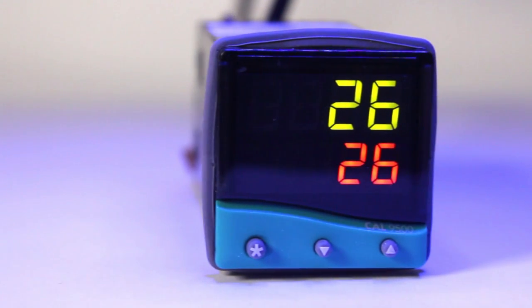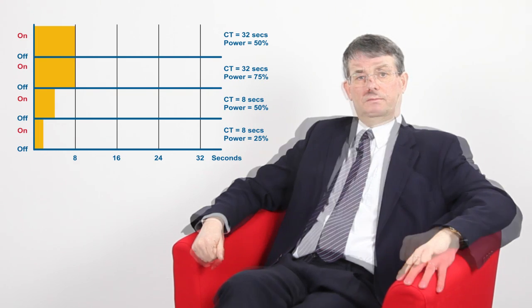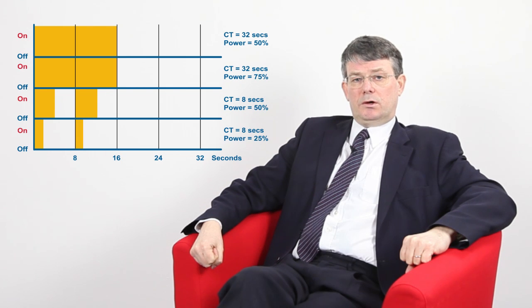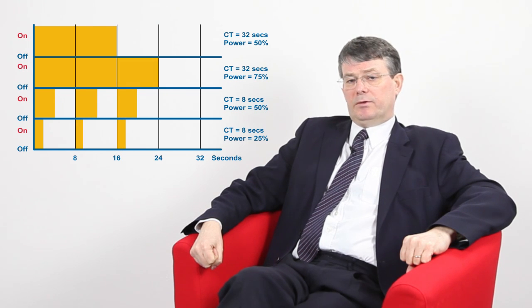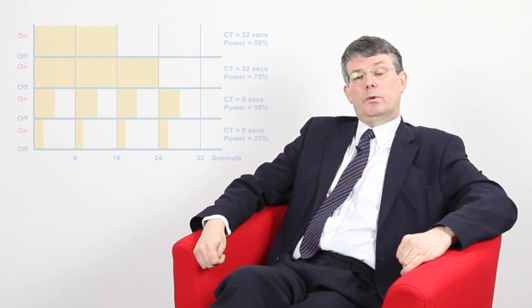There are some processes where it is not appropriate to use proportional control. For example, if you have a refrigerator and you are switching the compressor, you would have to use on-off control. A compressor cannot be turned on and off frequently, as would happen with proportional control. Even if the cycle time was set long, it would still switch more often than would be desired. For example, if you set your cycle time to 200 seconds, at 5% of power the output would only be on for 10 seconds, and at 95% the output would be off for 10 seconds. Neither would be good for the compressor.